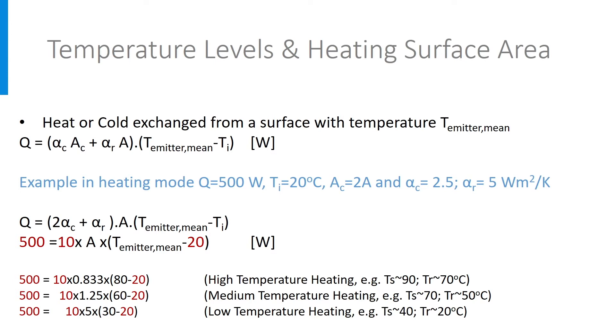In the second example, the radiator has an average temperature of 60 degrees. That could be a supply temperature of 70 degrees and a return temperature of 50, leading to a surface area of 1.25 square meter. And in the last example, the radiator temperature is only 30 degrees on average, corresponding to a supply at 40 and a return at 20 degrees, leading to a surface of 5 square meter.